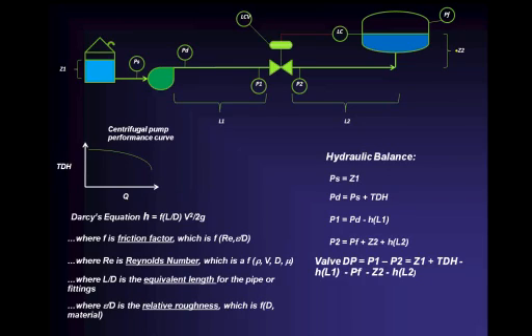All of that is your information, and therefore, in order to predict P1 and P2, you need to do a hydraulic balance. And ideally, you do that balance at a minimum at 2 flow points. The max flow you expect this valve to handle and the minimum flow you expect this valve to handle.